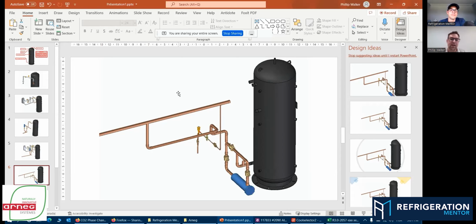So for typical design, if you're asking about velocity on our liquid, this is all done in K65. We're happy to work between 150 and 300 feet per minute. But once again, there's your liquid shell, and you can bypass it. And you'll see a little loop here, and that's really intentional for any type of oil coming through. The biggest oil occurrence you're going to see is at startup, where we have no load in the display cases at the beginning. We're putting our oil in, and it takes a while to balance the system, so you have a lot of oil circulating.